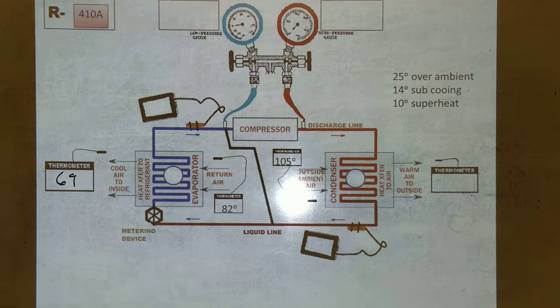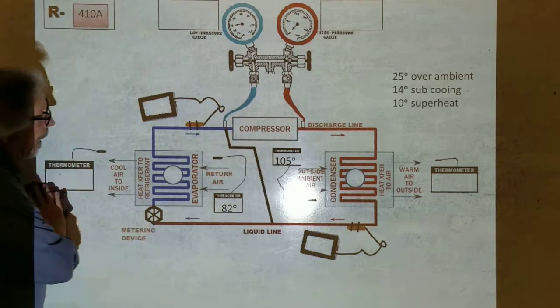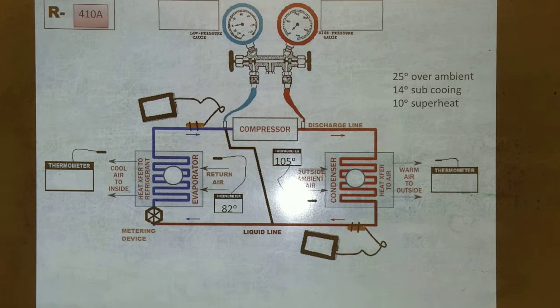So a lot of times the brokers or the management companies that call us say, we're gonna send a chart out for you. When you check your units out, we want the pressures on every single unit, and we want to log them and write them down on our checkoff sheet.